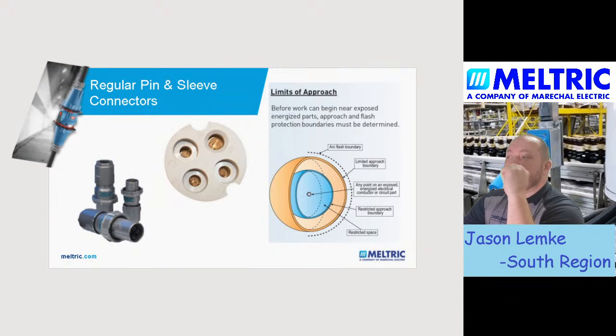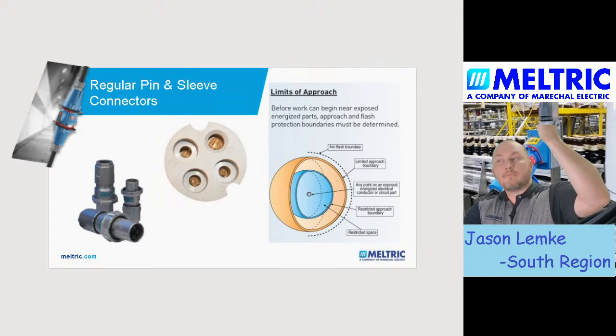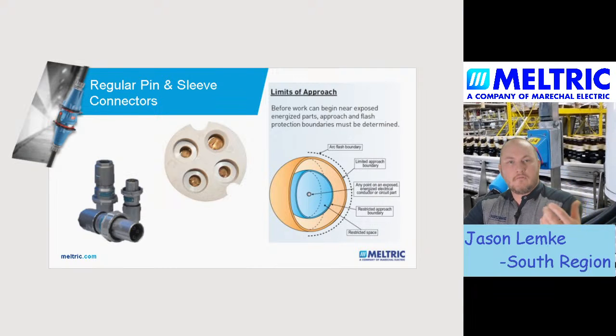So I can tell you that this is one of those things that I see all the time in the field, which is a receptacle on the wall. Maybe it's on a disconnect, maybe not. And maybe the disconnect's in the off position, but the lid is off of the pin and sleeve device. So you still have exposed conductors, and perhaps you don't have the lock in the off position. So you have exposed conductors with the potential for having those conductors be energized, and therefore operating inside of that space is considered working, and you have to be a qualified person to do work in a limited approach boundary. So I think that's a really unique and interesting feature about Meltric, and one of those big differences between a Meltric device or a switch-rated device and a pin and sleeve device is this ability to, when the plug has been removed, make sure that you're never going to be exposed to potentially live conductors.